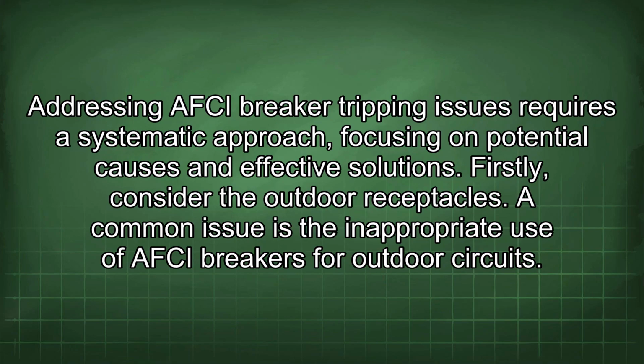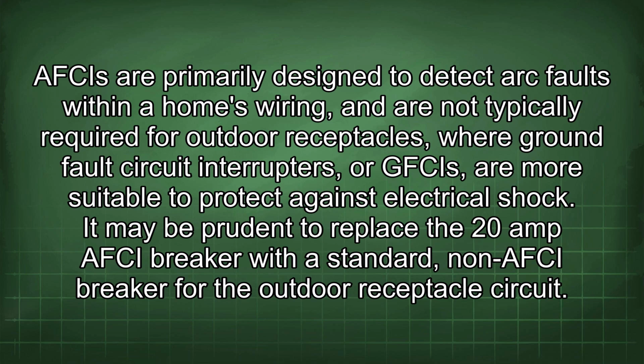Addressing AFCI breaker tripping issues requires a systematic approach, focusing on potential causes and effective solutions. Firstly, consider the outdoor receptacles. A common issue is the inappropriate use of AFCI breakers for outdoor circuits. AFCIs are primarily designed to detect arc faults within a home's wiring and are not typically required for outdoor receptacles, where ground fault circuit interrupters, or GFCIs, are more suitable to protect against electrical shock.